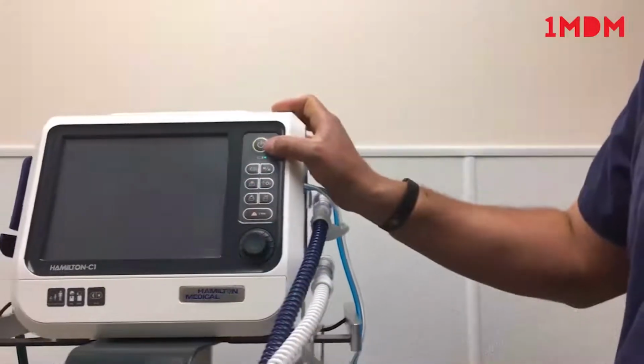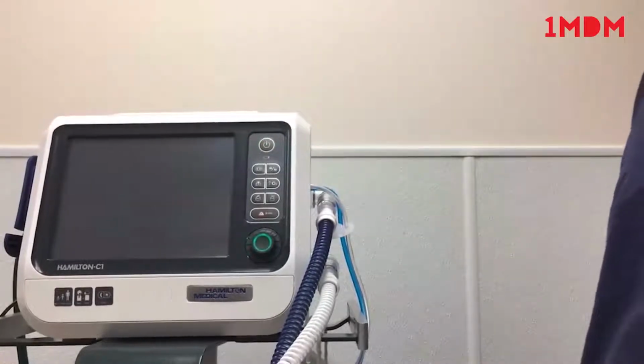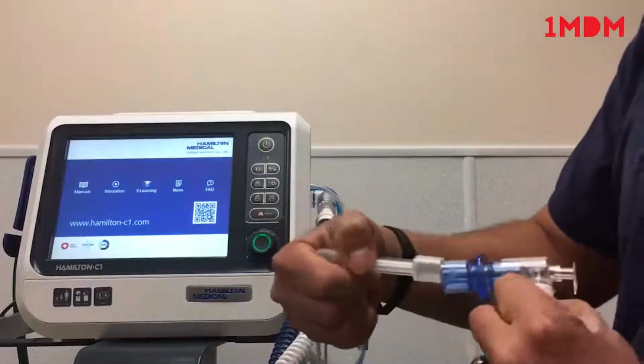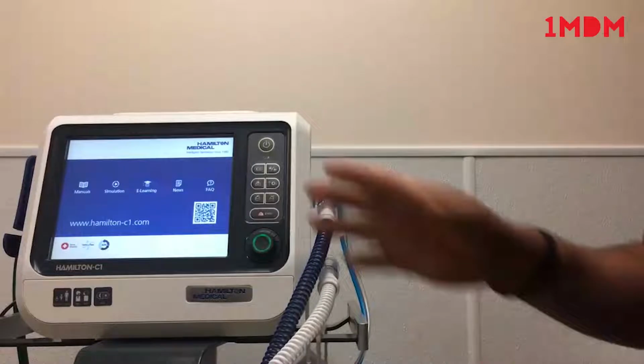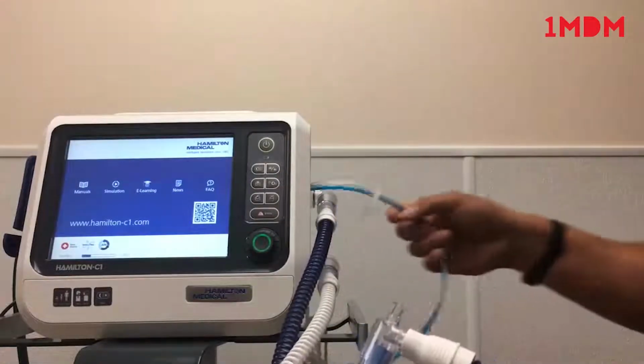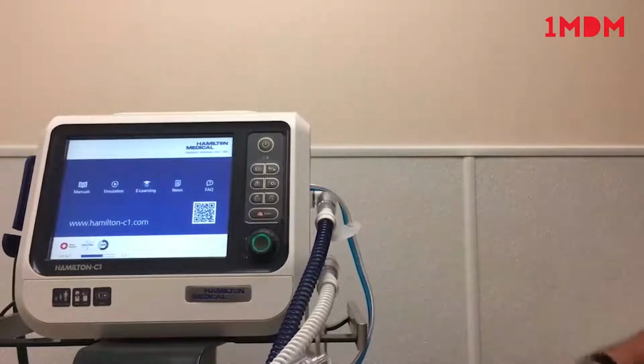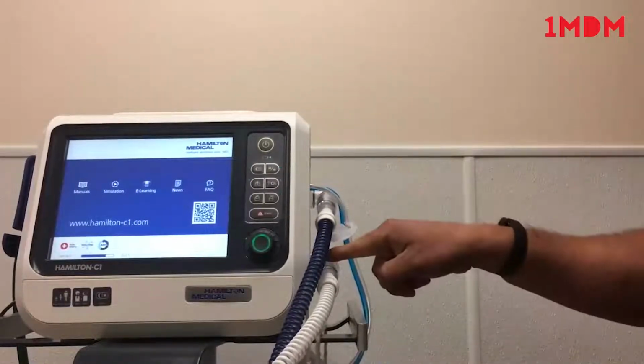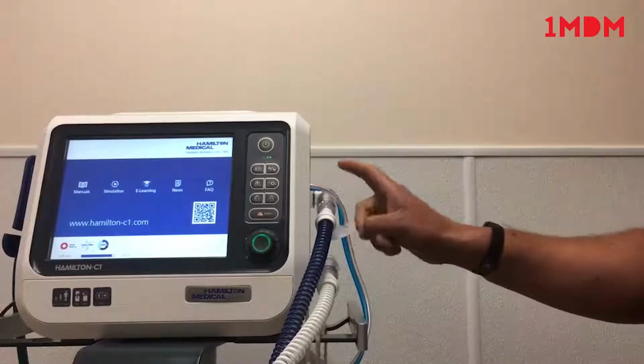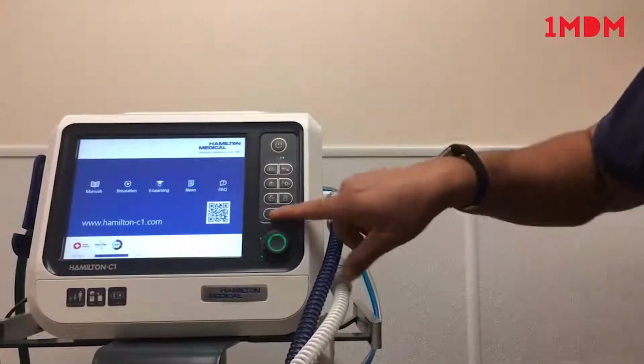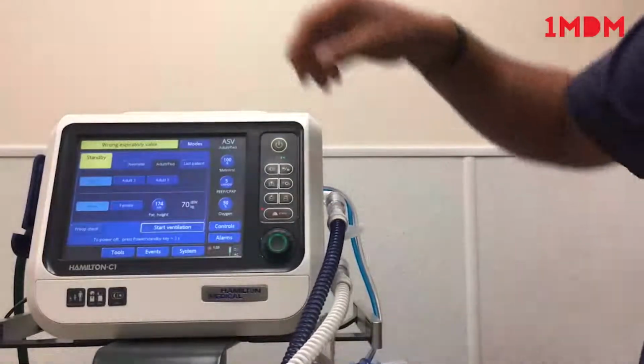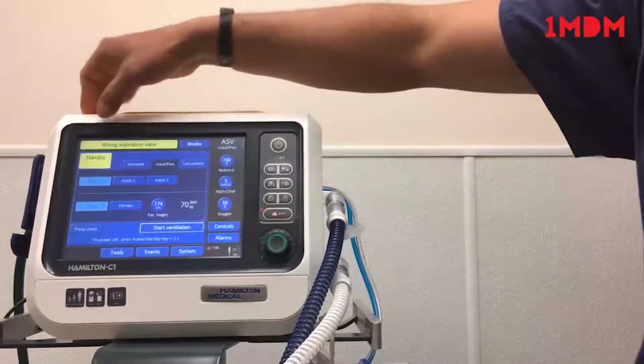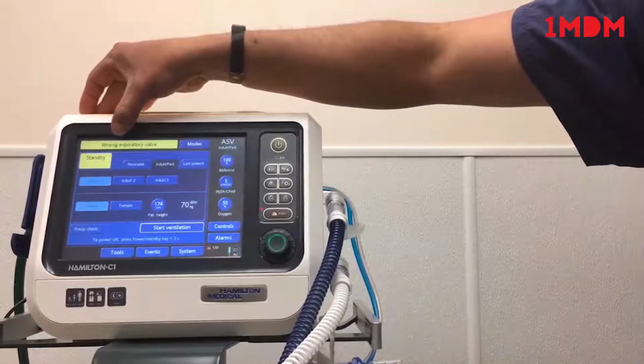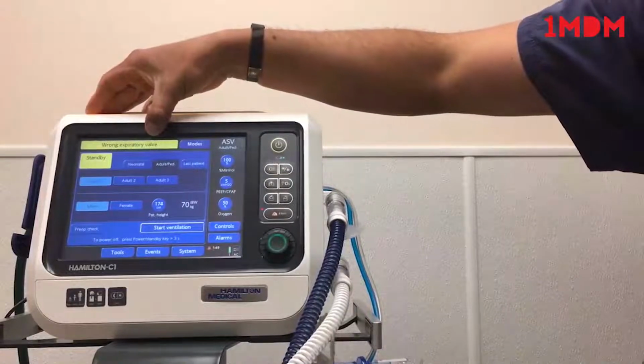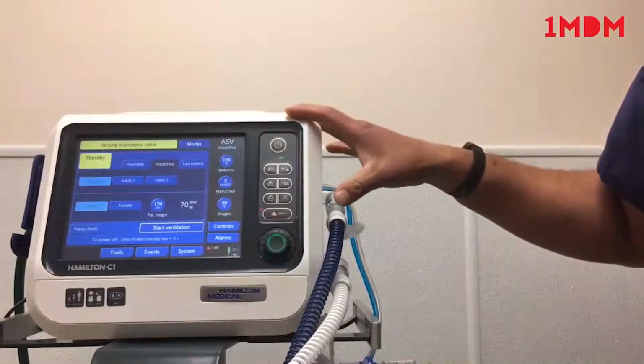Now that everything's attached, we're going to go ahead and power the C1 ventilator. It's going to take a minute here. So all the attachments are nicely fastened. Make sure that you use an expiratory filter both on the inspiratory and expiratory limb. Go ahead and hit your silence button. And we're going to look at the display. The display here says wrong expiratory valve. So that lets you know that we are hooked up to the neonatal circuit.